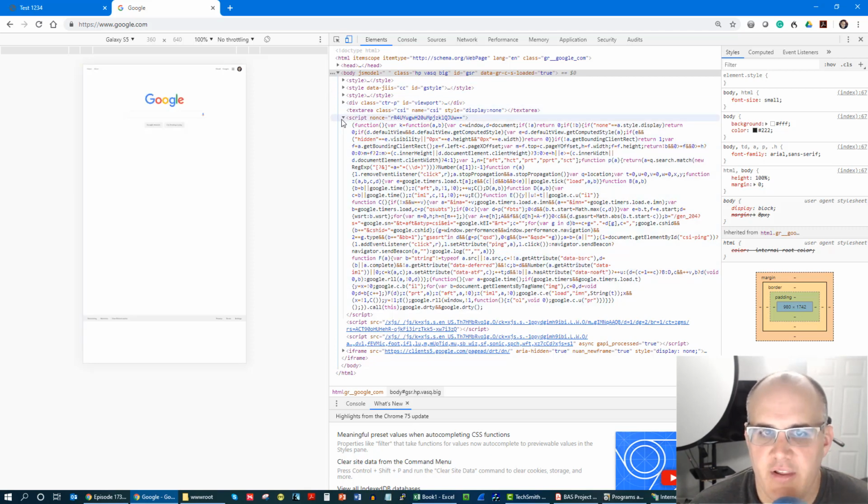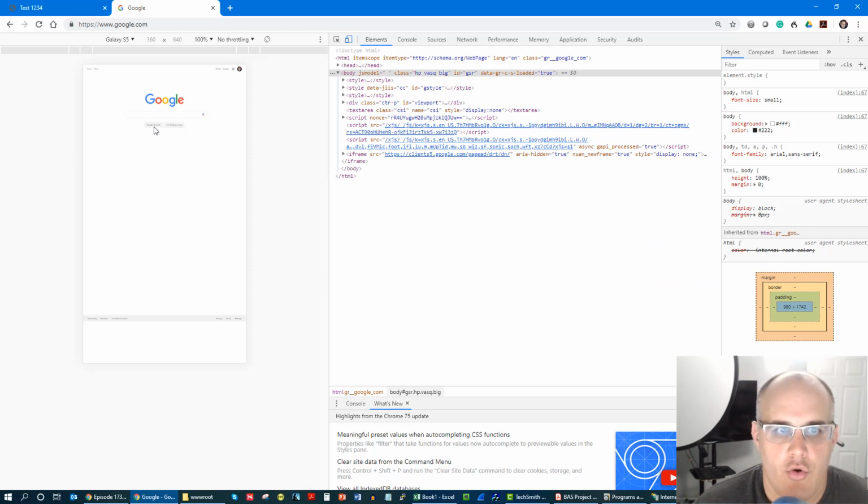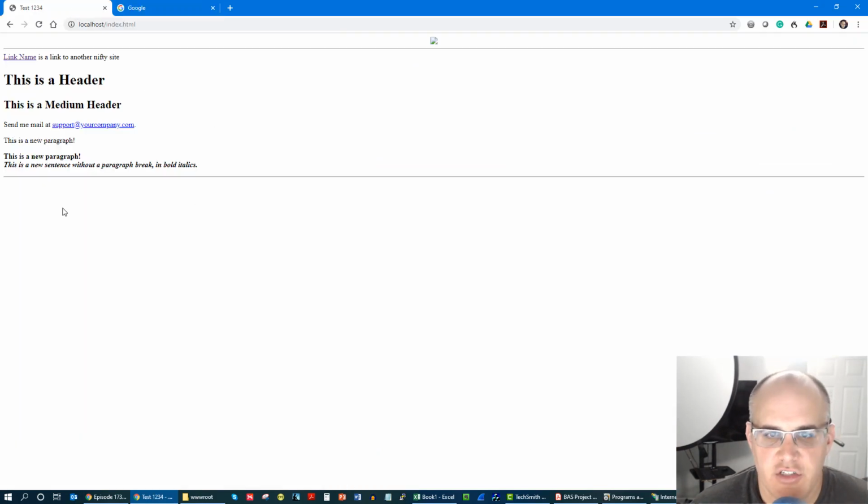That allows us to send data, like if we want to update a zone temperature point, we can enter that data and then click a button, and that JavaScript will take that and call a server function. So we would have our BAS software running on the server, and it would call a server function that would then make this BAS accept that zone temperature change.